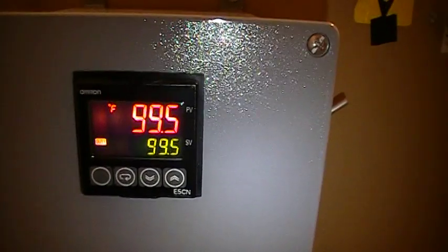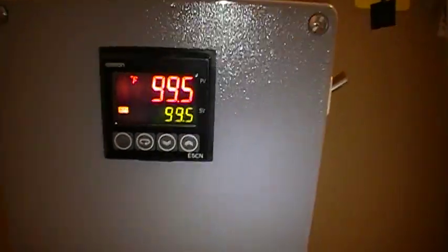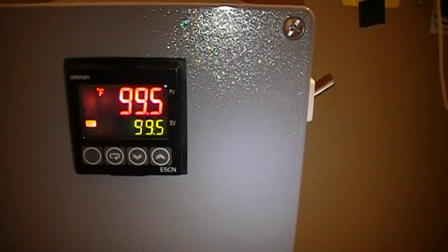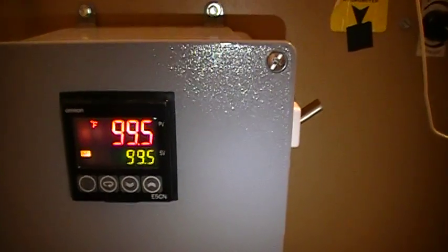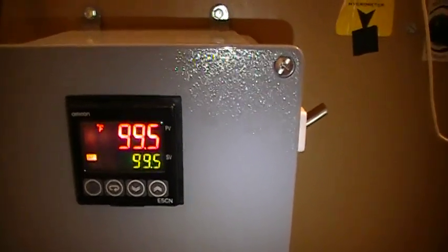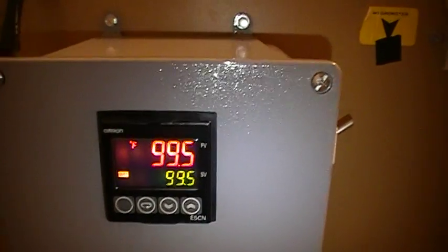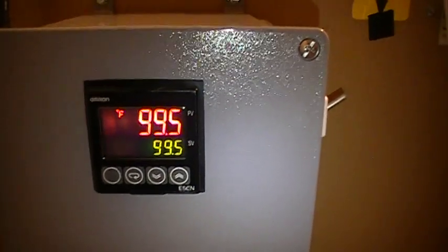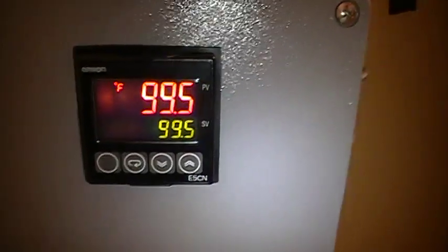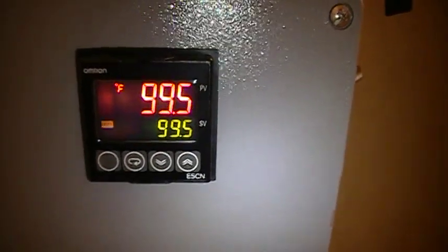This little unit has an auto tune, which allows through the auto tune system, once you set it to auto tune, it will program itself for about 10 minutes by experimenting with different timing and load resistance on the heating element in there, so that it's able to determine exactly what the optimum amount of current and the time frame of that current that's needed to send to the element to keep the temperature precisely at 99.5.